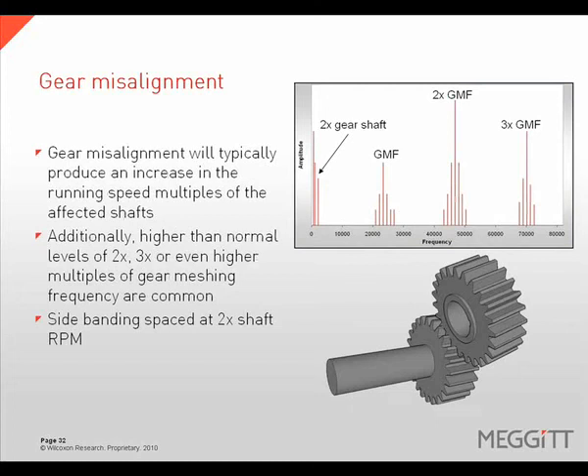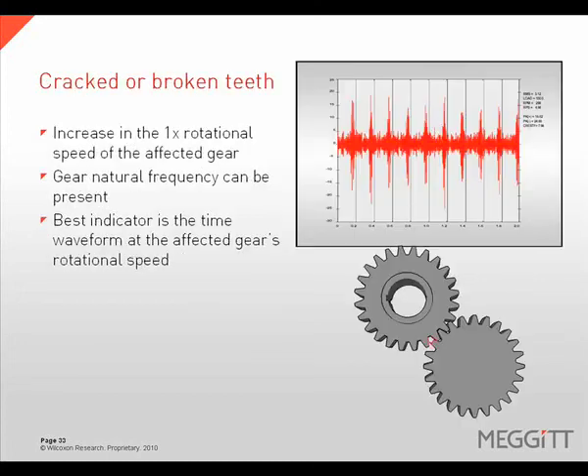Gear misalignment will produce an increase in running speed harmonics of the affected gears. Higher than normal levels of 2 times, 3 times, or even higher multiples of gear mesh frequency are common, with sidebanding spaced at 2 times the shaft's rotational speed. Cracked or broken gear teeth will increase the amplitude of the 1 times rotational speed vibration peak, and the gear's natural frequency can also be present; however, the best indicator of cracked or broken gear teeth is found in the waveform, with impacting spaced at the rotational speed of the damaged gear.